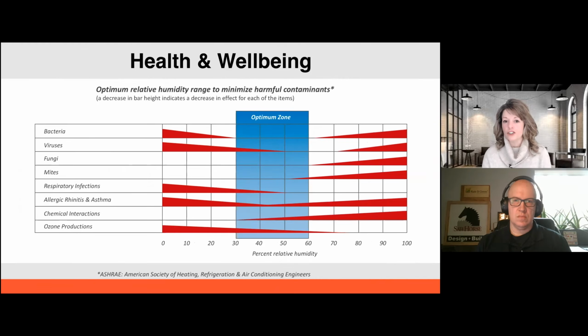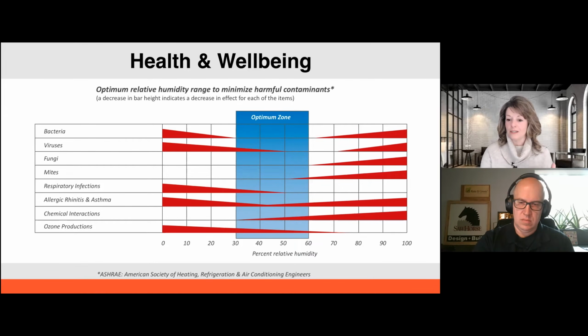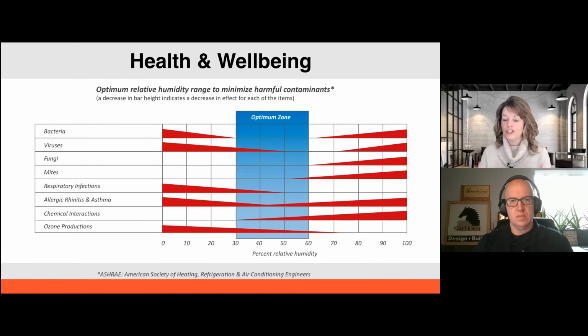So this is the Sterling chart. Everybody's seeing it out there right now. It really focuses on the health of relative humidity and what our optimum range is. And again, we have 30% here on the low range, which is going to be wintertime. There are no temperatures associated with this, but we need to understand that 30% is in the wintertime and that 60% is in the humid times of the year. We don't want people in Minneapolis trying to get to 60% relative humidity in January. So we need to understand that these are associated with temperatures and times of the year.